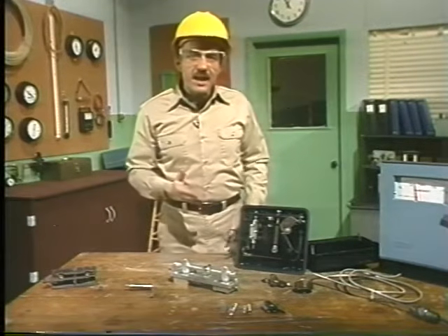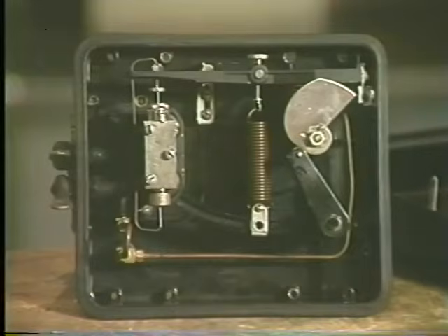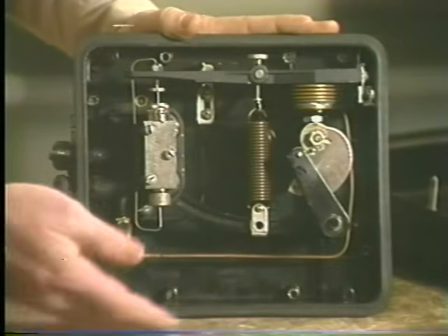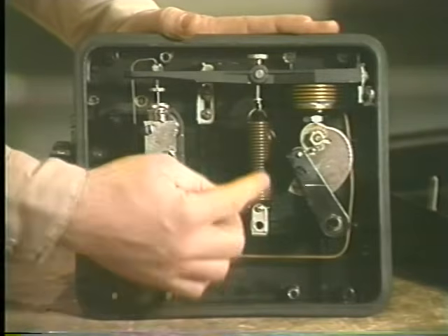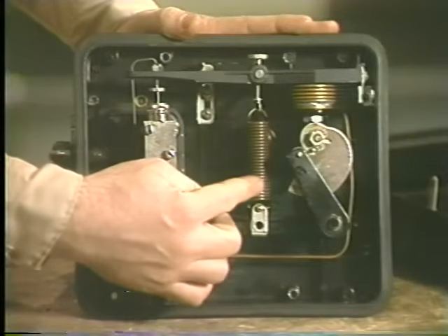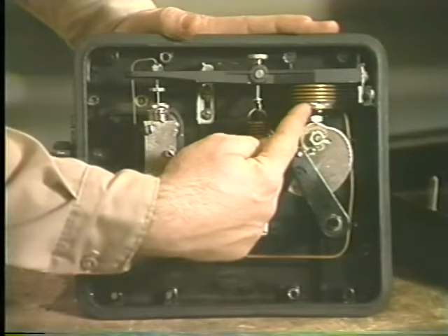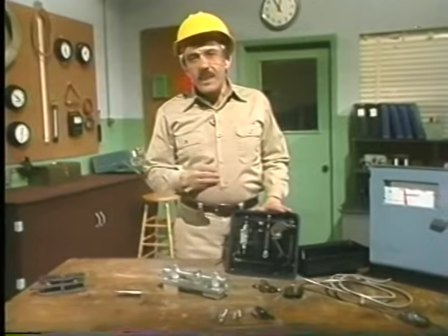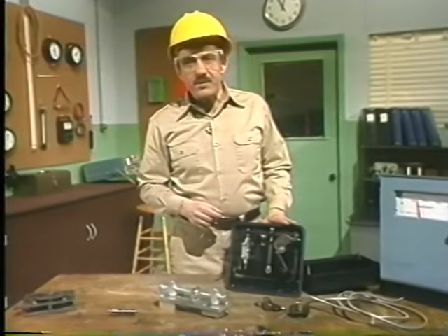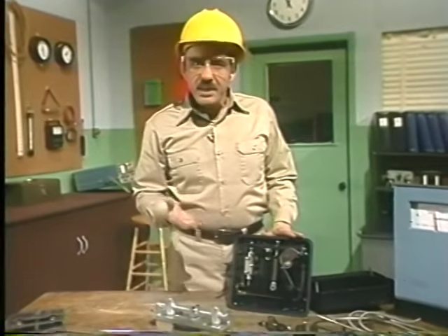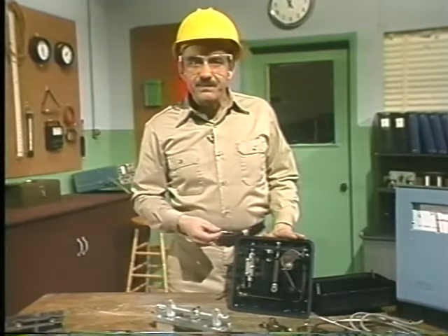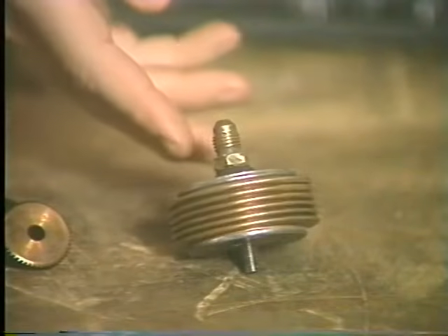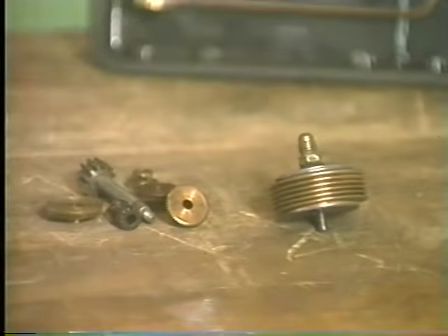So, when you take the cover off of any pneumatic control instrument, you may find any number of different shapes and sizes of springs. For example, in this positioner, this spring is designed to oppose the deflection of the input bellows and beam. Now, in addition to different springs, you'll also find a variety of beams, links, and levers, as well as some of the components we didn't look at in detail: bellows, gears, and so on.